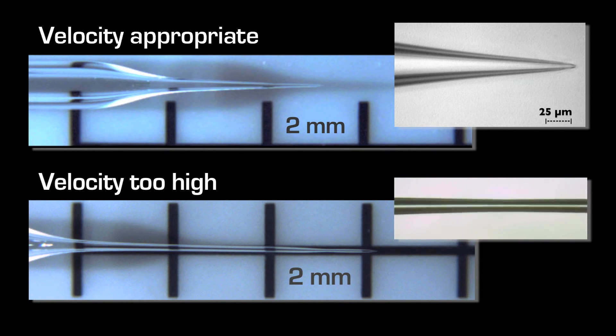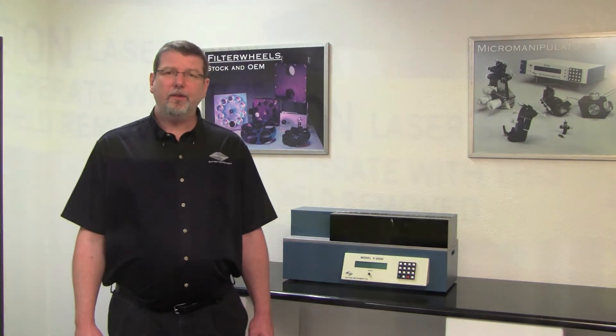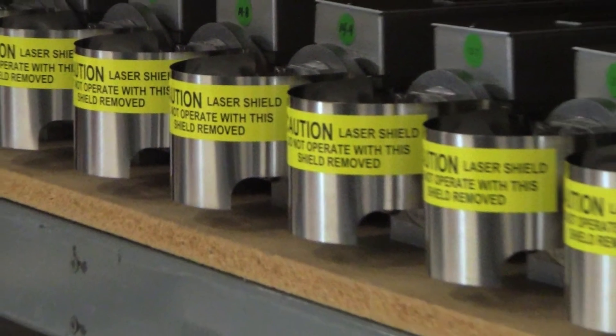Let's finish with a word of caution. The P2000 Puller is a class 1 laser product, which means in everyday operation the laser radiation is safely contained inside the enclosed housing. Redundant interlocks and other safety features reliably protect the user from exposure to the laser beam. To show pipettes while they are being pulled, we have produced the detailed images in our videos using a specially modified instrument running under controlled conditions in our laser safety lab. The 10W CO2 laser in the P2000 Puller produces an invisible beam that is powerful enough to melt quartz glass, meaning it's easily strong enough to cause serious burns to your skin and especially to your cornea. We don't want you to get hurt, so please do not disable the safety features on your puller at home.